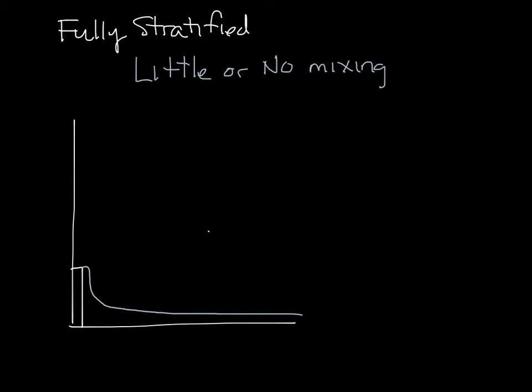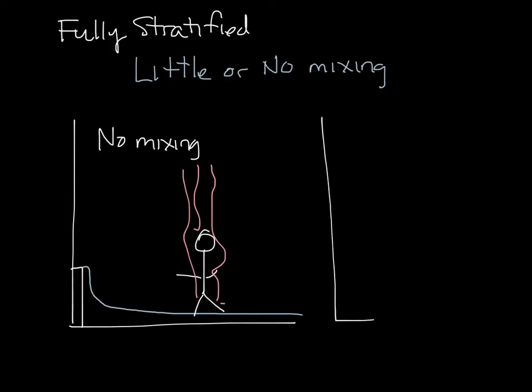When it comes to a heat source, like a person, the air and the heat from that person will rise. There's no actual mixing going on, and the temperature rises as you go from floor to ceiling. It would be a high temperature change right at the floor, and then it would just rise up and be stratified pretty much throughout the entire space.